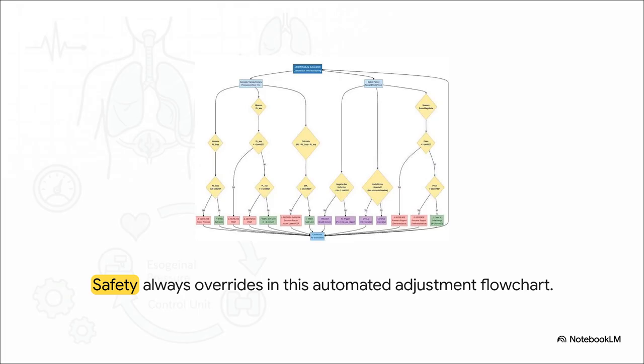You've got this continuous stream of data from the esophageal balloon feeding directly into the dual pathways of lung protection and diaphragm protection. But the main thing I want you to take away from this logic is the overarching rule: safety always wins. The algorithm is built with super strict conflict resolution. If achieving a certain lung recruitment target would push the transpulmonary driving pressure too high, boom, the algorithm initiates a priority override. Driving pressure safety limits always take precedence.